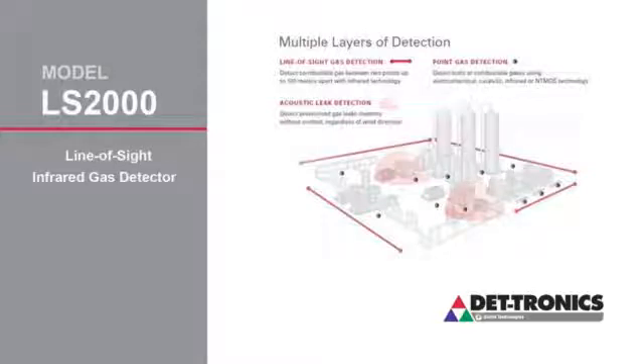With a point detector, you need to have an accurate concentration of gas where it's important that you know what type of gas and how much of it is there. With an acoustic detector, you have less information about that gas leak. You need a pressurized gas leak, but you have an expanded range of detection. You can think of an acoustic detector as a sphere, and whereas with a point detector the gas has to physically contact the product, with an acoustic detector we're listening for that hissing sound made by a pressurized gas leak.